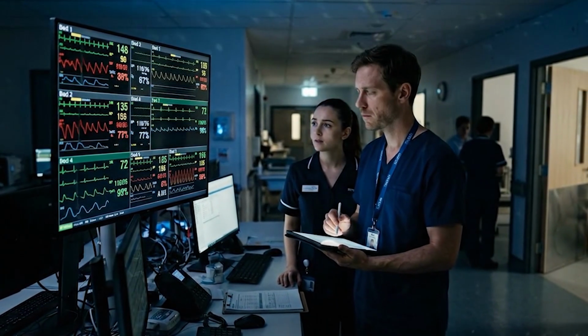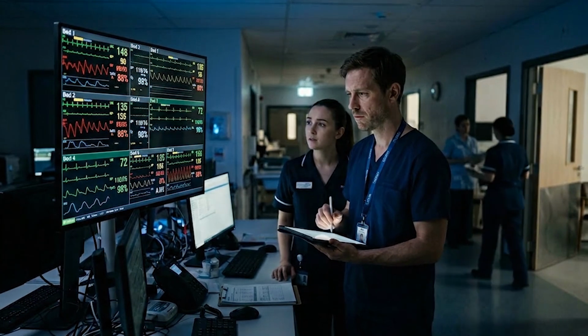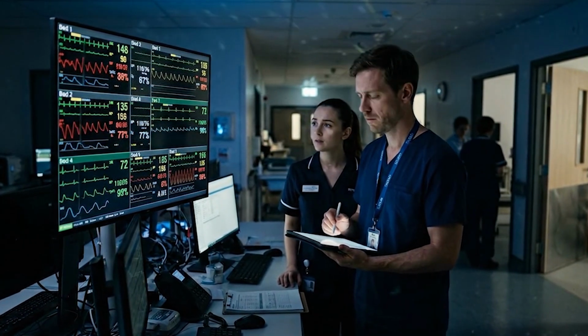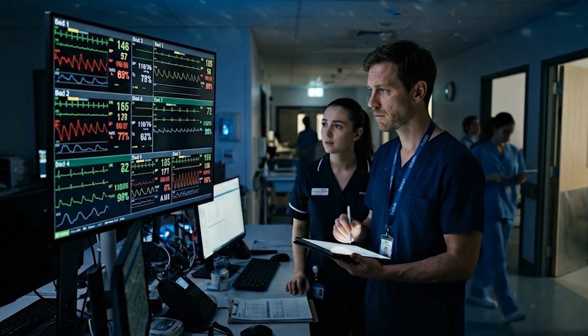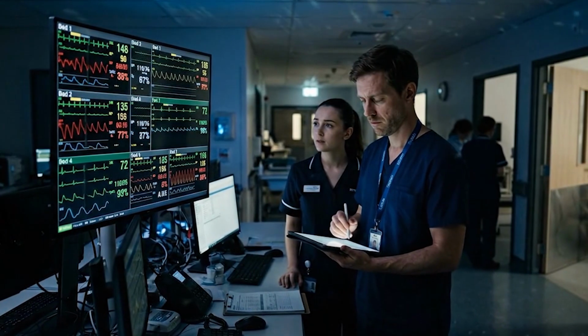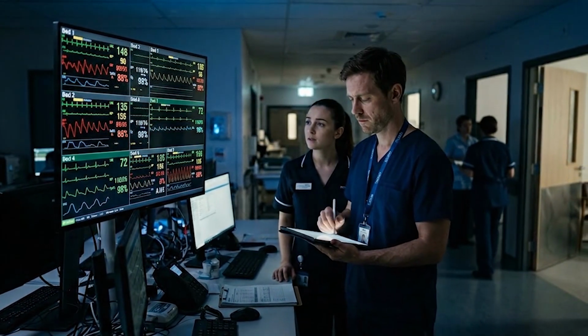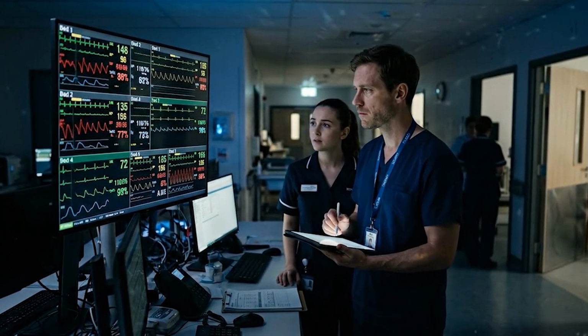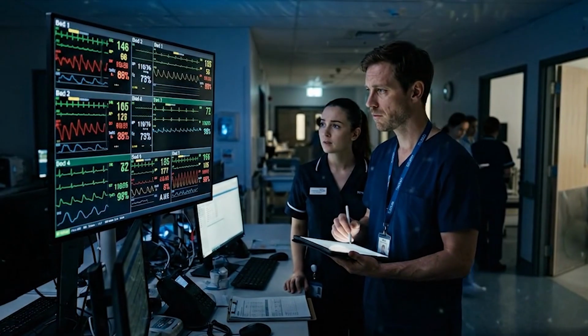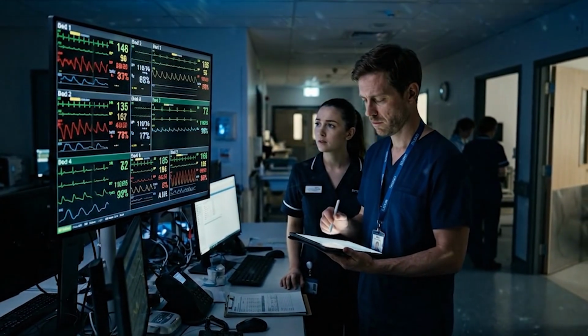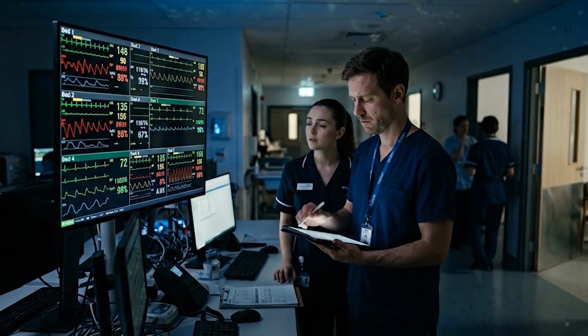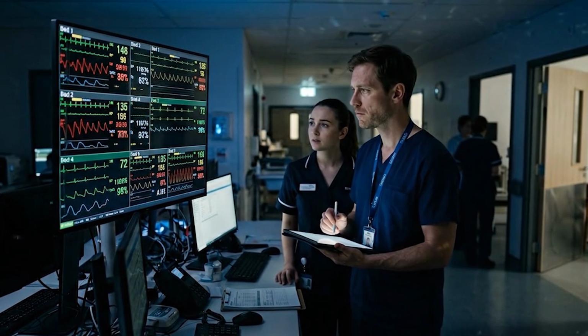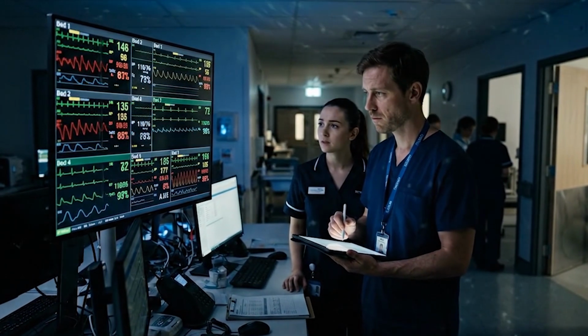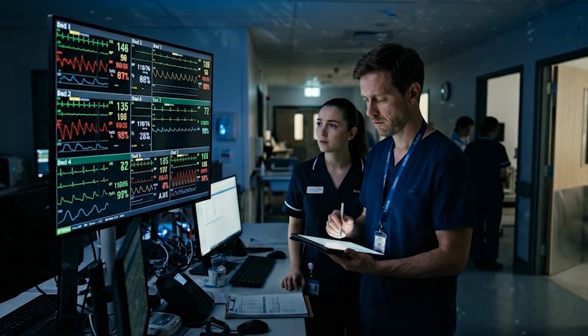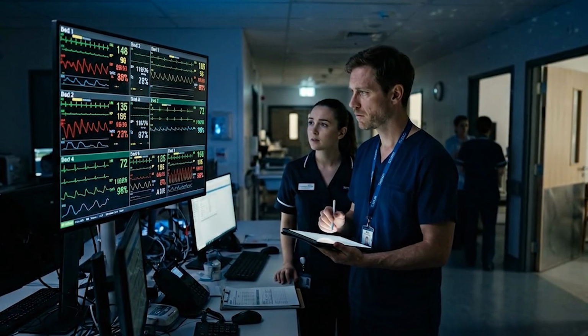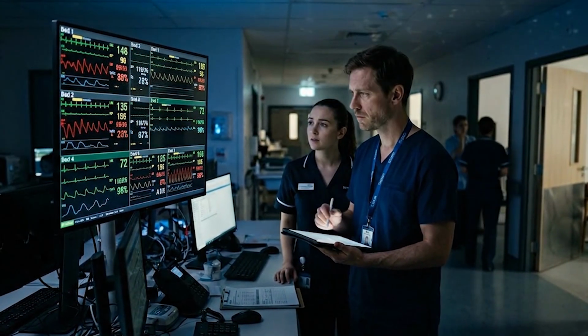On April 3rd, the Phantom appeared on a second unit. I was doing routine calibrations on the 5th floor, the general medicine ward, a 40-bed unit in the original hospital building, older equipment, a mix of Philips and GE monitors. Bed 22 was empty. Its monitor, a GE Carescape B650, an entirely different manufacturer, different hardware platform, different software, different network, was showing a heart rate of 72, blood pressure 118/76, respiration 14, SpO2 98. The same numbers, the same patient, on a different brand of monitor, on a different floor, in a different building, on a different network.